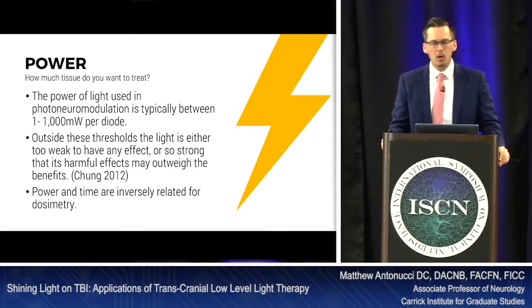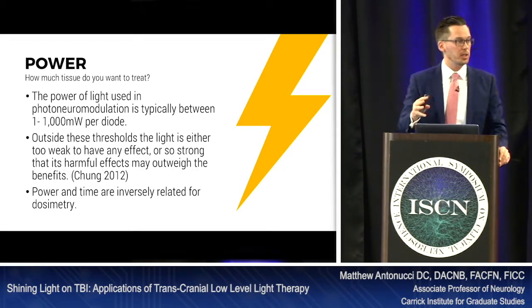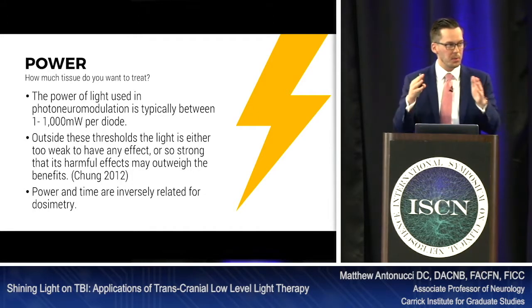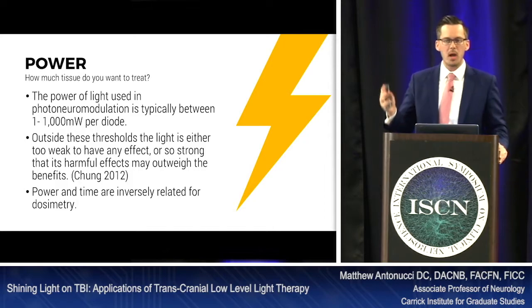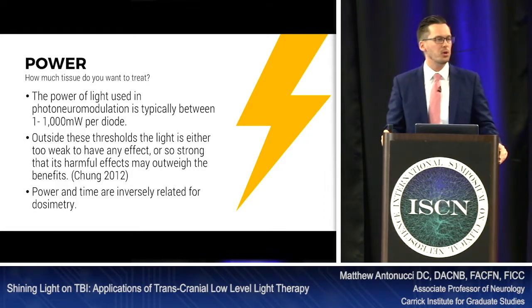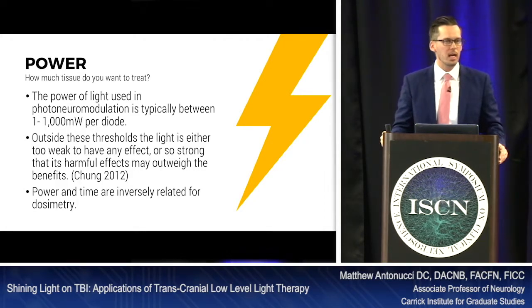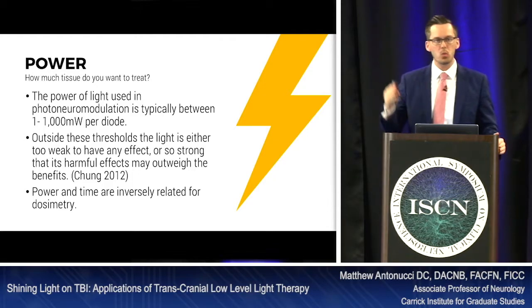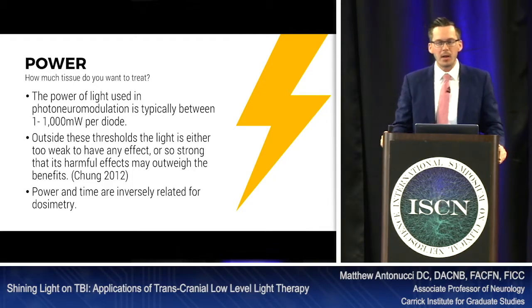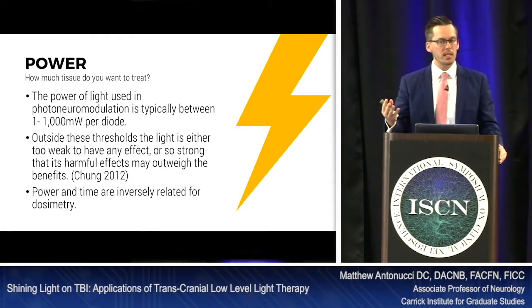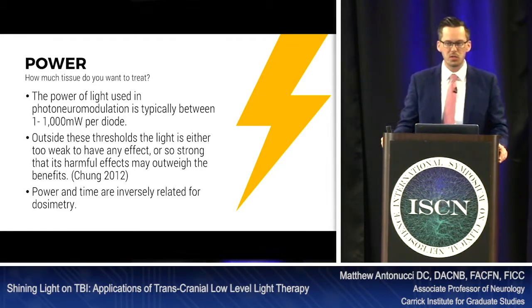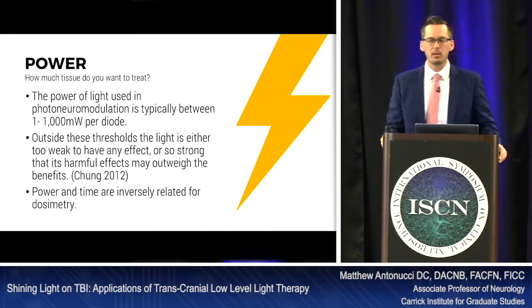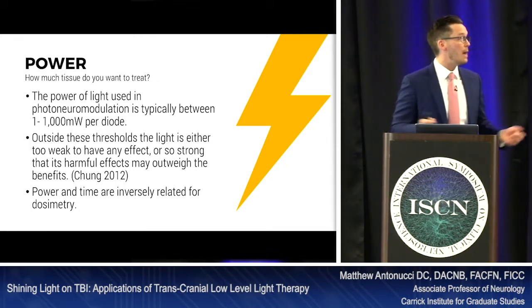Now, power — how much tissue do we want to treat? The power of light used in photoneuromodulation is roughly one milliwatt to 1,000 milliwatts per diode — a one milliwatt to one watt spectrum. Outside these thresholds, the light is either too weak to have any effect or so strong that harmful effects may outweigh the benefits. This is from Chung, 2012.